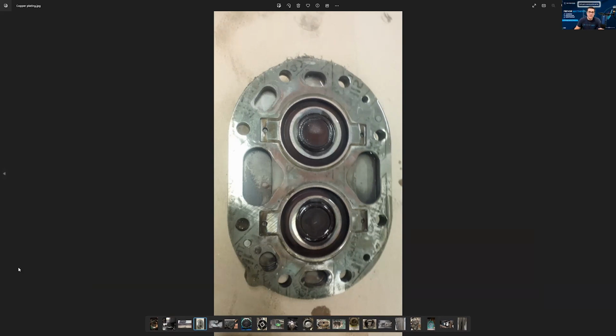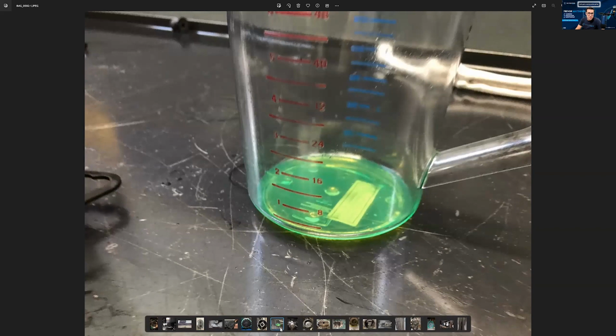You start seeing this stuff, you've got to be thinking, what did I do on my install? Or who did the install? Because this is stuff that comes up years down the road. And for me, I call this contamination in a system too. Even though there are some manufacturers that say, okay, well, we can use dyes in it. For me, it's contamination. You should have refrigerant and oil in your system, unless it's an oilless system.